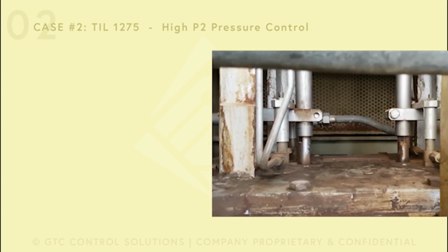TIL 1275. The protection against high P2 pressure control during startup, and then the control of the pressure in high and low conditions in normal operation. But the main thing is avoiding excessive fuel or high P2 pressure during startup. This TIL also makes sure that the P2 pressure is below 6 psi before the unit starts.